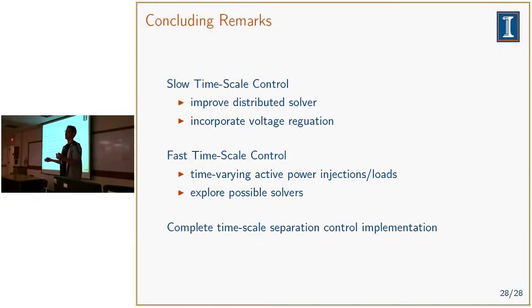Choosing that tap position would be for a particular loading of the system. So could it be that at one loading you have a great solution, but it's really horrible at a different loading? If you don't update in between as the system loading changes, you'd be worse off overall.